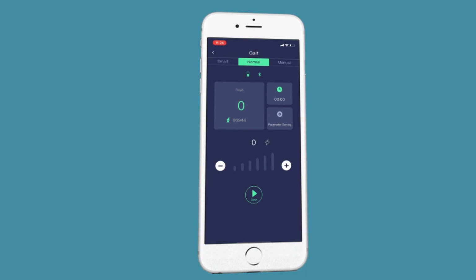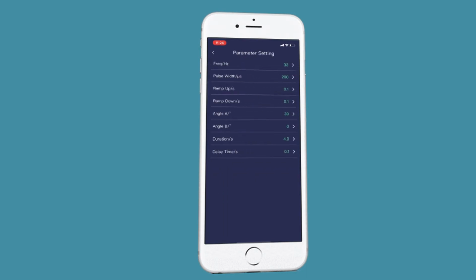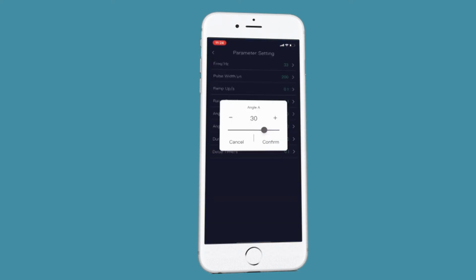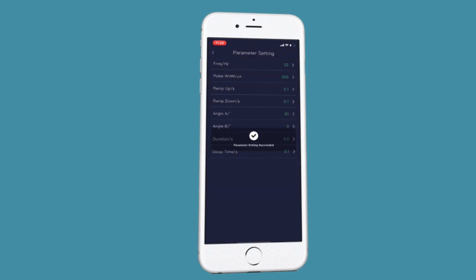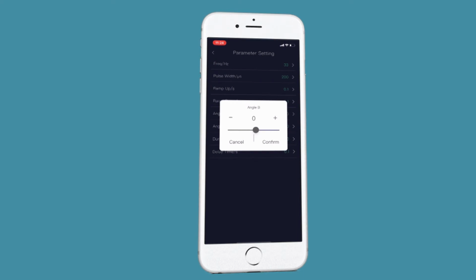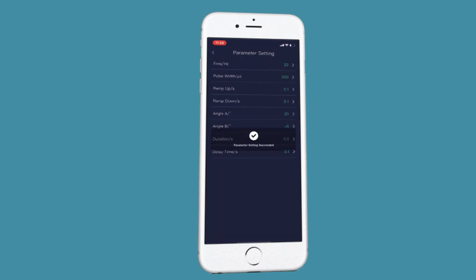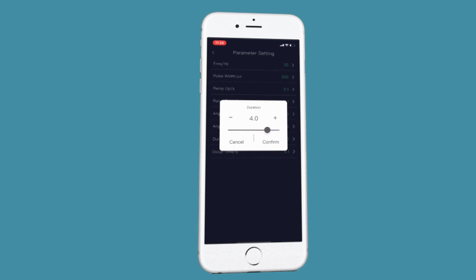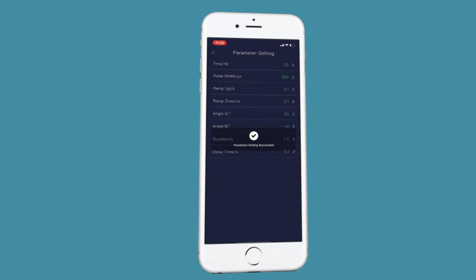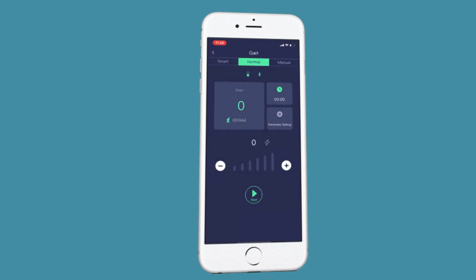Under normal mode, in all of these modes, you can quickly change parameters. You can see in normal mode, you can change many additional parameters, such as angle on, which is angle A, and angle off, which is angle B. So I just changed angle A to 20 degrees, and these are real degrees. And then angle B, remember, you can also change it to negative degrees. So angle B, I want the device to turn off a little bit sooner, so I change it to -5. And then duration, for some of your slow walkers, it may be 3 to 5 seconds. I'll change it to 3.5 seconds.